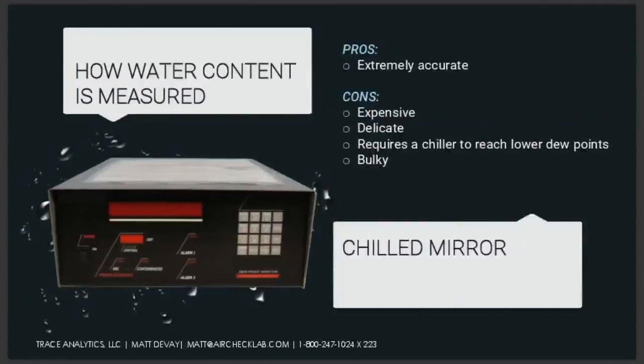All right, chilled mirrors. This is a dew point hygrometer, chilled mirror type. These work by having a mirror that gets very cold as the air flows past it. As the mirror chills, it will condense water vapor out of the airstream. Then there's a light beam that bounces off the mirror to a sensor, and the sensor will detect when the mirror is fogged. So when the mirror fogs, you know what temperature that is. That also happens to correspond to your dew point. These are pretty much the gold standard for really accurate water vapor measurement.